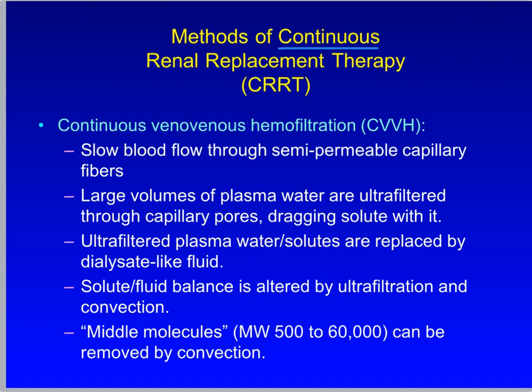Today, the main methods of CRRT that we use are CVVH and CVVHDF, and we'll look at a brief description of each. In continuous veno-venous hemofiltration, or CVVH, venous blood flows at a slow rate through a hemofilter consisting of hundreds of semi-permeable capillary fibers, just like a dialyzer, but smaller. Negative external pressure can be used to create a gradient across the membrane that allows plasma water to be ultrafiltered and removed, dragging solute with it.